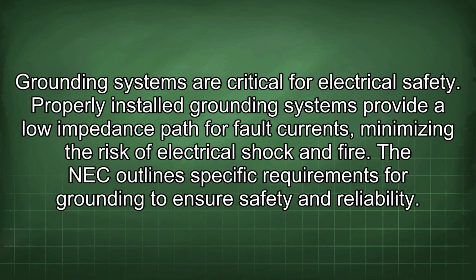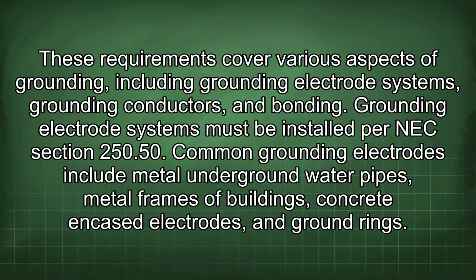Grounding systems are critical for electrical safety. Properly installed grounding systems provide a low impedance path for fault currents, minimizing the risk of electrical shock and fire. The NEC outlines specific requirements for grounding to ensure safety and reliability. These requirements cover various aspects of grounding, including grounding electrode systems, grounding conductors, and bonding.